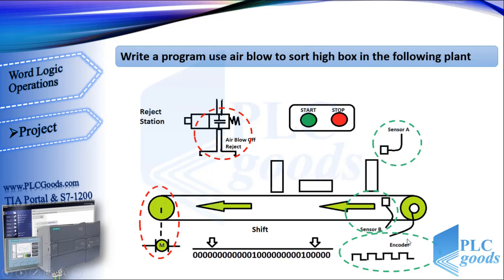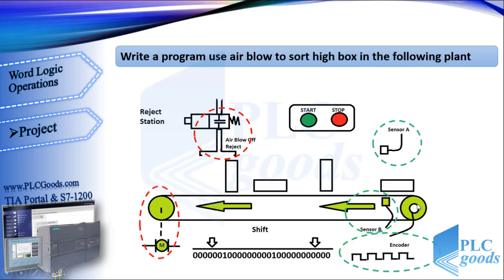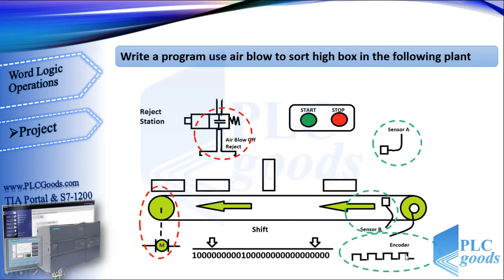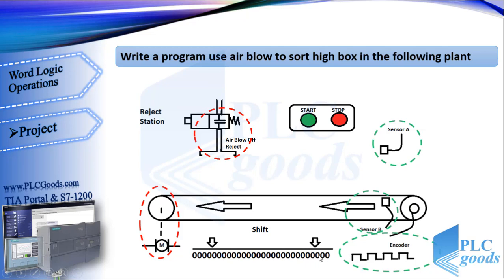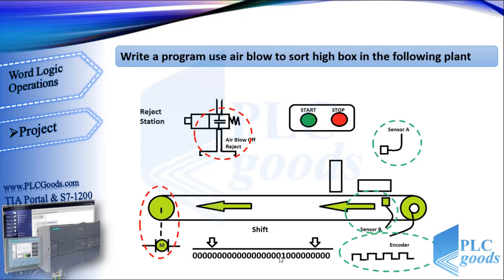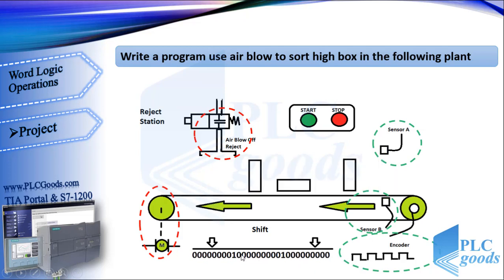And finally, an encoder which is connected to conveyor. It sends regular pulses when the conveyor is turning. So if sensor B detects a box on the conveyor, we can use pulses from encoder, and a shift instruction, to have box position.